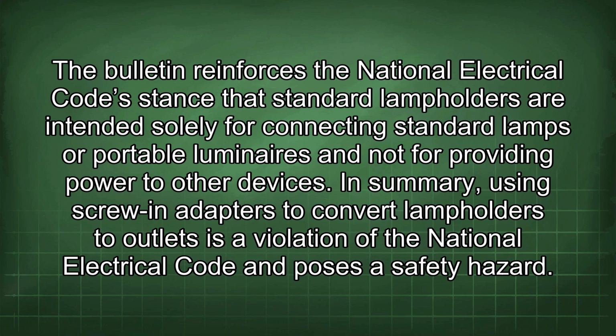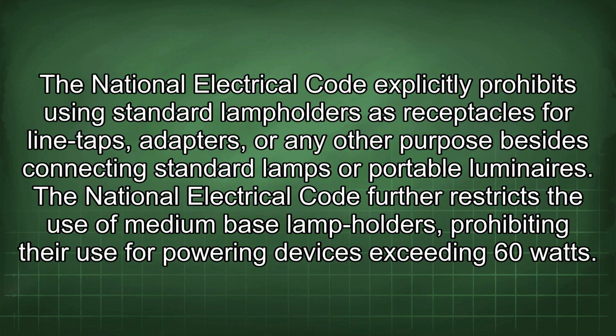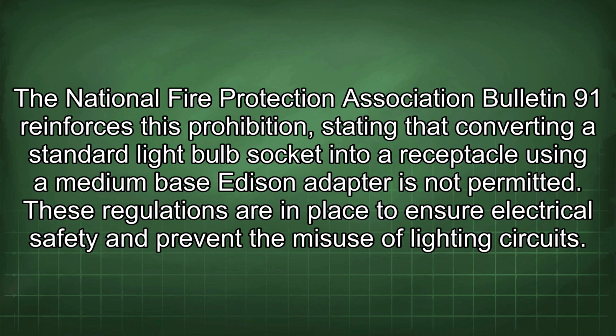In summary, using screw-in adapters to convert lampholders to outlets is a violation of the National Electrical Code and poses a safety hazard. The National Electrical Code explicitly prohibits using standard lampholders as receptacles for line taps, adapters, or any other purpose besides connecting standard lamps or portable luminaires. The National Electrical Code further restricts the use of medium-base lampholders, prohibiting their use for powering devices exceeding 60 watts. The National Fire Protection Association Bulletin 91 reinforces this prohibition, stating that converting a standard light bulb socket into a receptacle using a medium-base Edison adapter is not permitted.